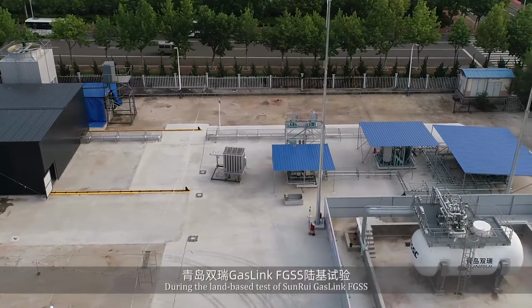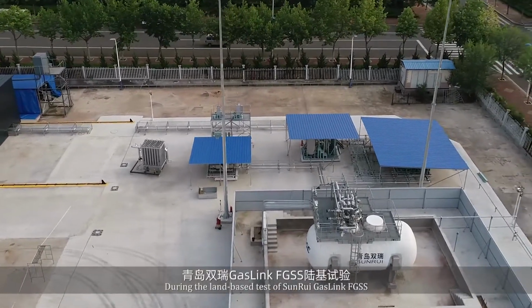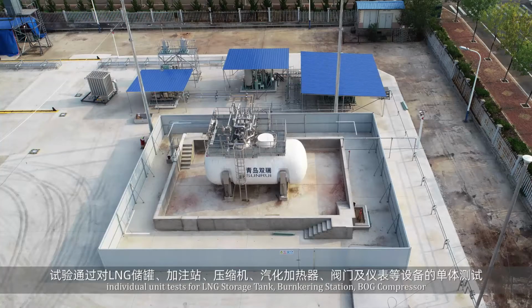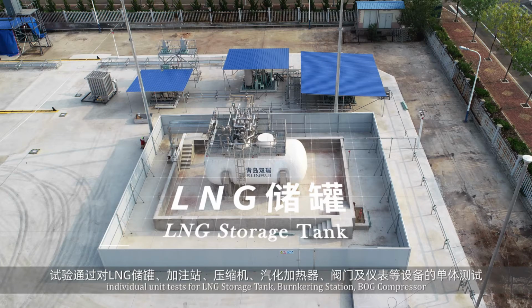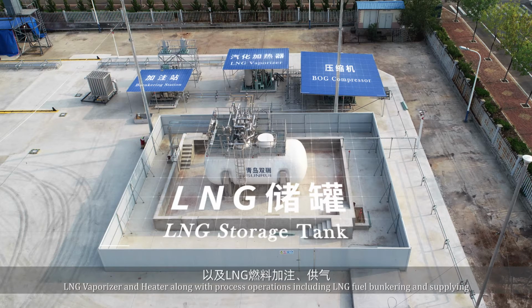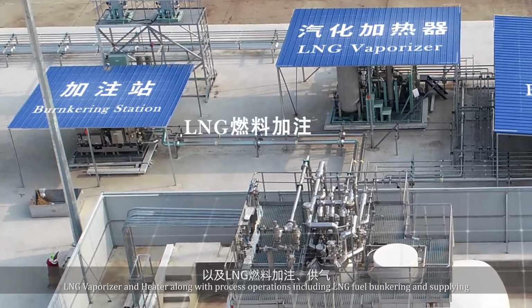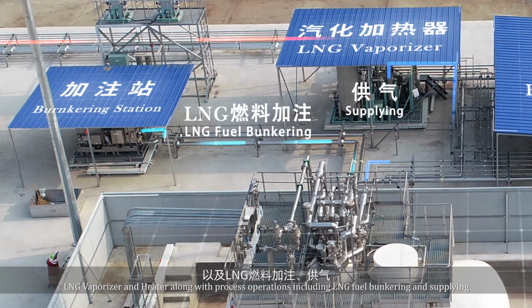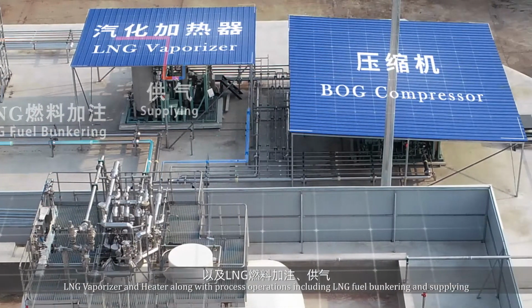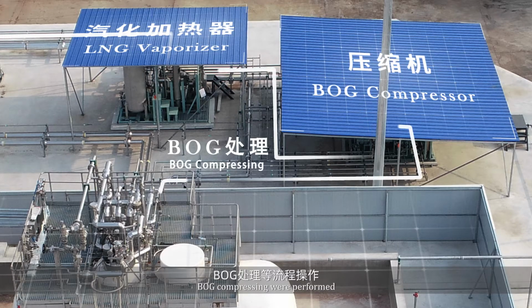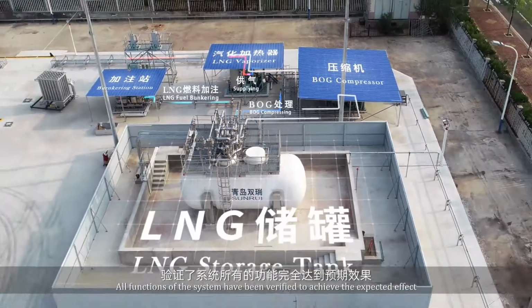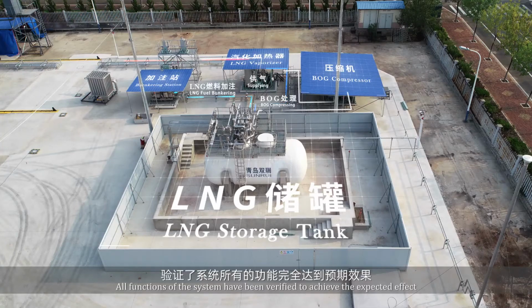During the land-based test of SunRui Gaslink FGSS, individual unit tests for LNG storage tank, bunkering skid, BOG compressor, LNG vaporizer and heater, along with process operations including LNG fuel bunkering and supplying and BOG compressing, were performed. All functions of the system have been verified to achieve the expected effect.